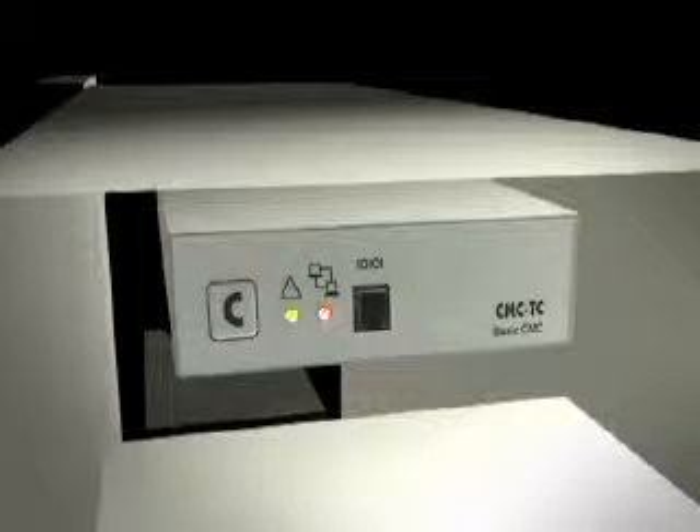The LCP Plus 300mm wide module consists of a heat exchanger fed from an external chiller system and six fans, which circulate the hot air via the heat exchanger. Intelligent modules monitor the fans and flow rates, displayed on a touch-sensitive LCD screen on the front of the LCP Plus. The LCP Plus is connected to a standard 1200mm deep enclosure and pulls the hot air from the server exhaust and cools it via the heat exchanger. It's been specifically designed to blow cool air across the whole height of the enclosure to ensure there's no chance of any hot spots developing.